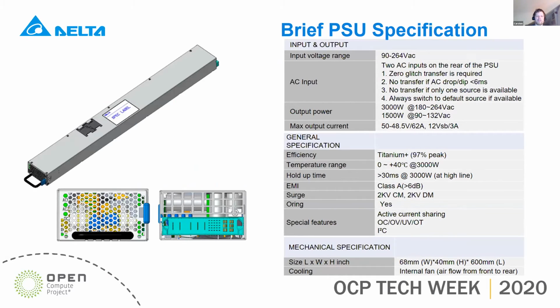Our power supply, as Ming already said, has the specification shown on the right hand side, mainly with an ATS, an automatic transfer switch. From an engineering point of view, what's tricky is the high requirement for hold-up time. 30 milliseconds means we have to install a lot of bulk caps and make some tricky design choices to increase the hold-up time.